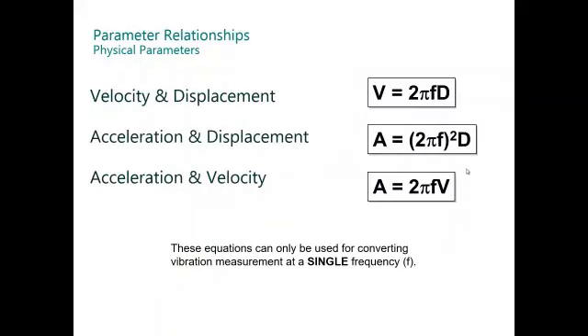The parameter relationships between velocity and displacement and acceleration are related with the frequency. Velocity is 2πfD. The acceleration is 2πf squared times D, and the acceleration is 2πfV. This is a very useful equation to calculate one parameter into another.